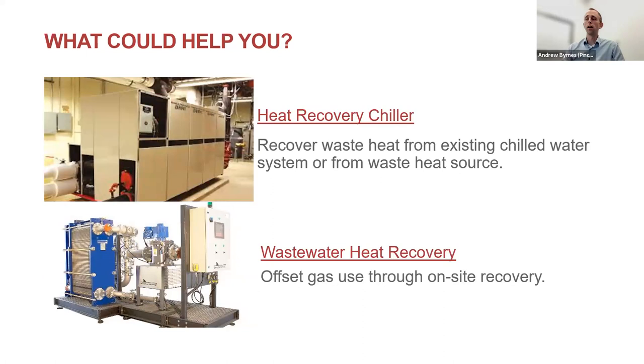Heat recovery chillers are also great to look at when replacing existing chillers, or if you have a building with a four-pipe heating and chilled water system - there's a lot of value in adding a heat recovery chiller to share energy between those systems. Wastewater heat recovery is another option, and a great source of heat for decarbonization projects.